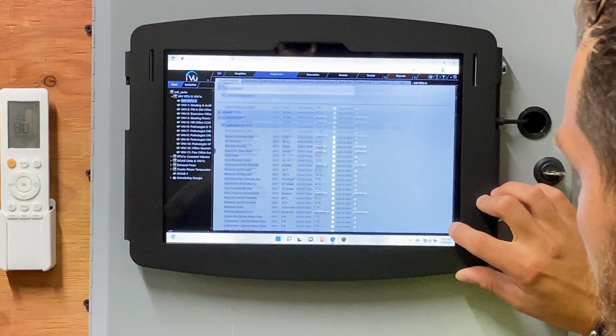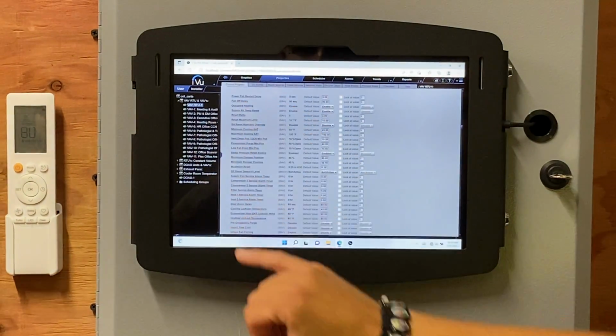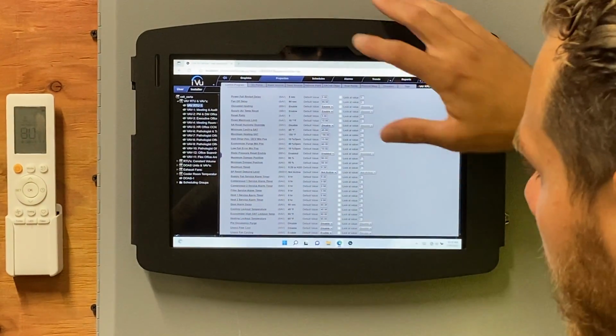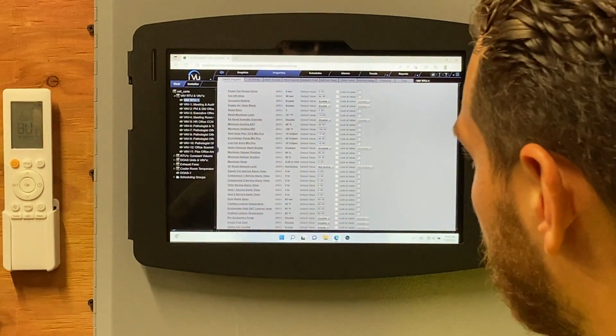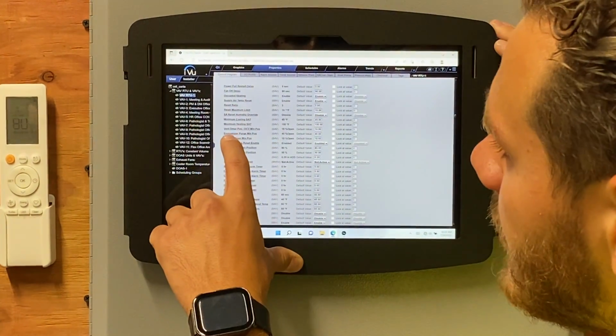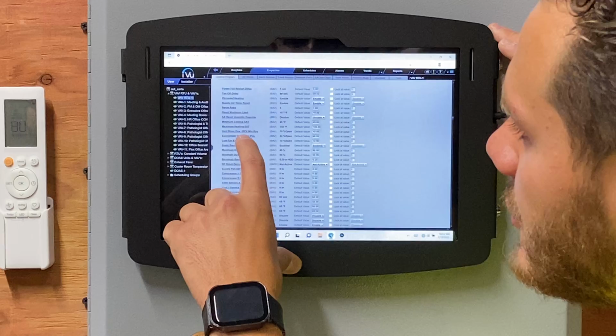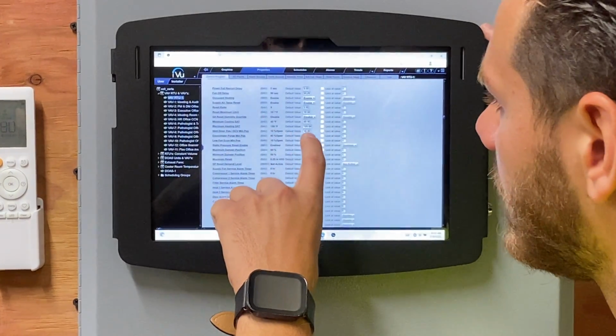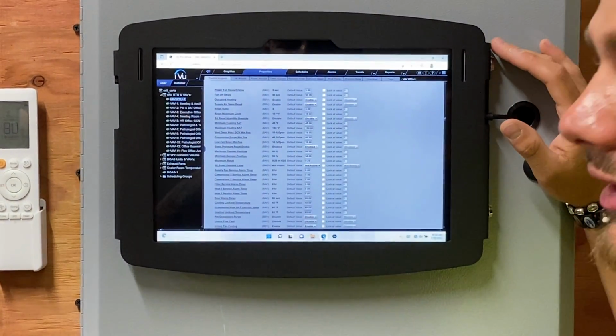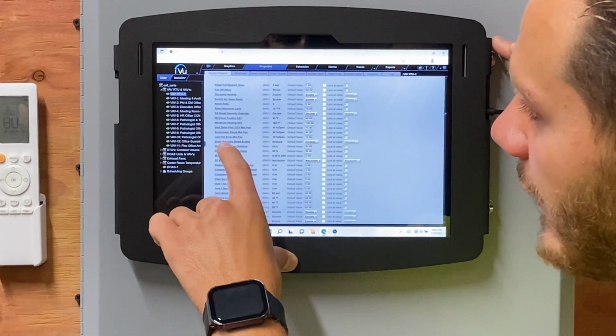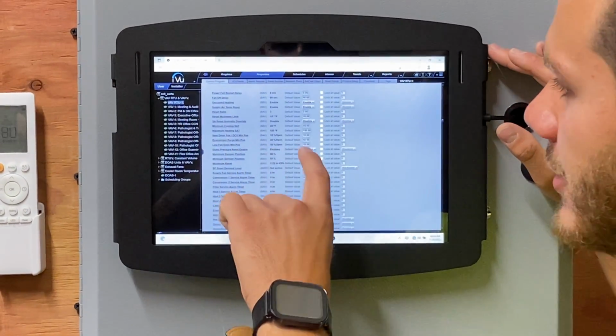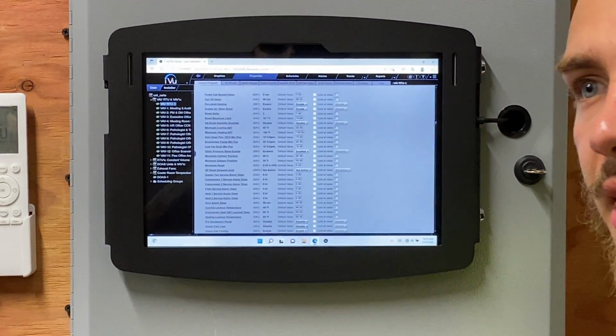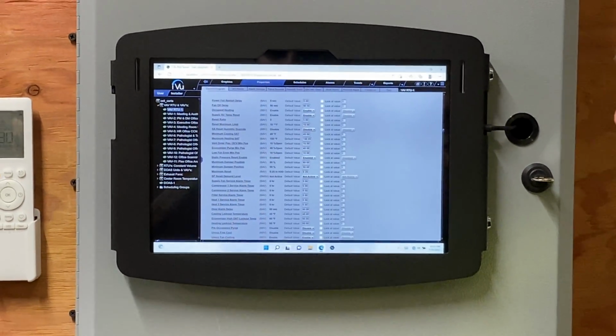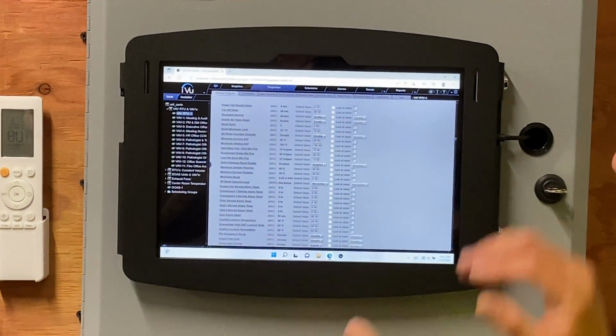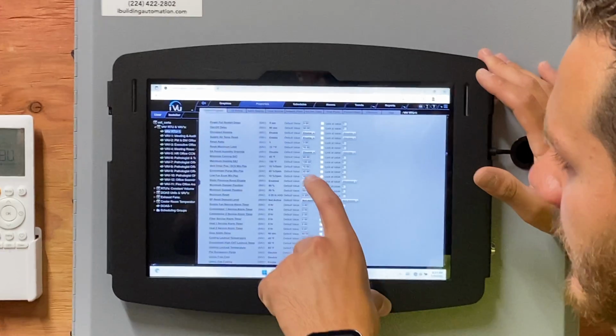In your unit configuration, you do have a lot of points here, and on the left you can reference the name. So the outside air damper, that position that I was talking about, is right here. So you have a vent damper position, DCV minimum position of 10%. And then you have another point that is called low fan economizer minimum position. And that's just gonna simulate if you're in a low fan operation, where do I want my economizer? And we have both of those values actually set to 10.